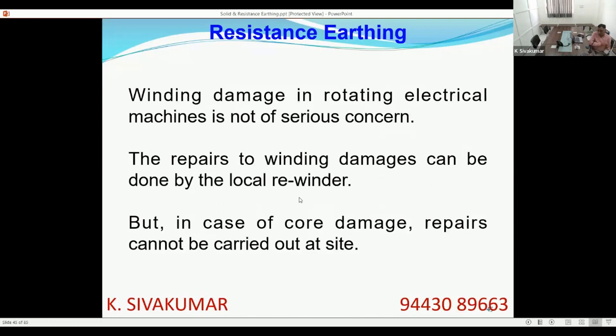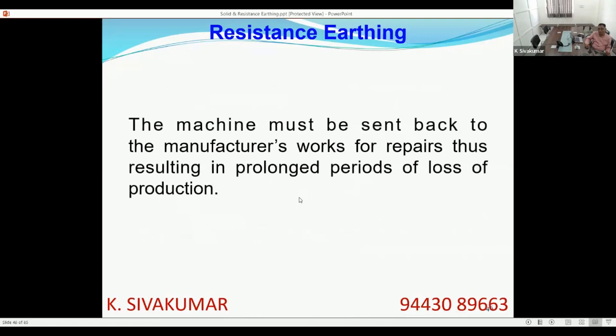But in case of core damage, the local rewinder does not have the expertise or the facility to repair the core. Generally, any core damage, the machine must be sent back to the manufacturer. The machine manufacturer also may not take up the repair job immediately, so he will give priority to production. As and when his staff are available, he will allot them for repair work. Even if they have a dedicated service team, there is the transit time from your facility to the manufacturer's works, the time taken for repair, and the transit time back.